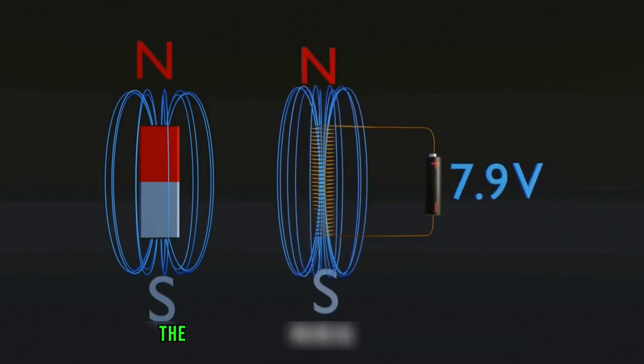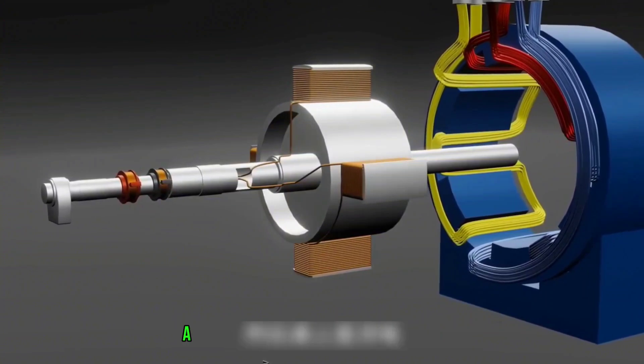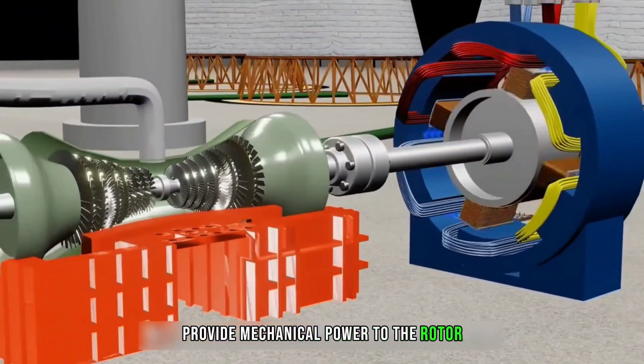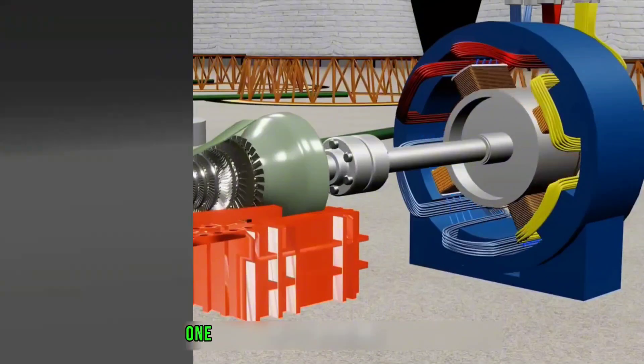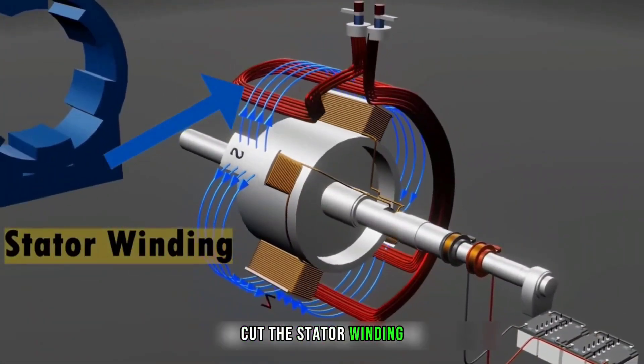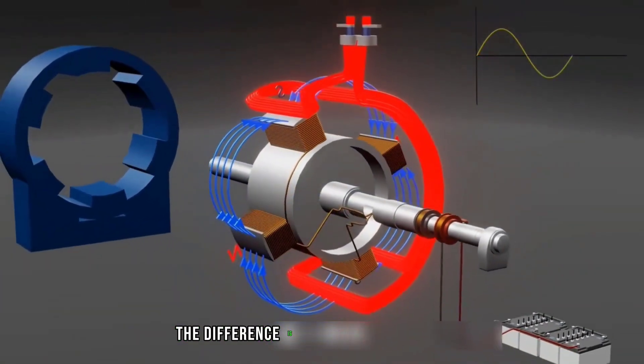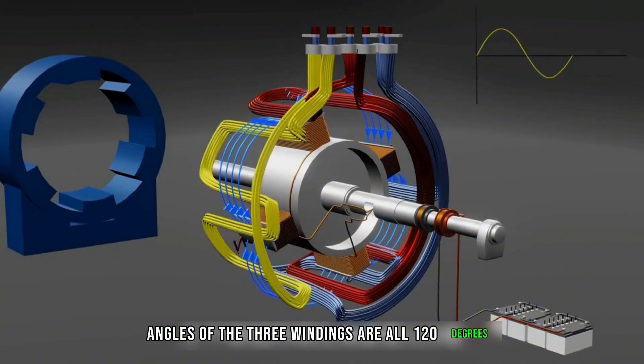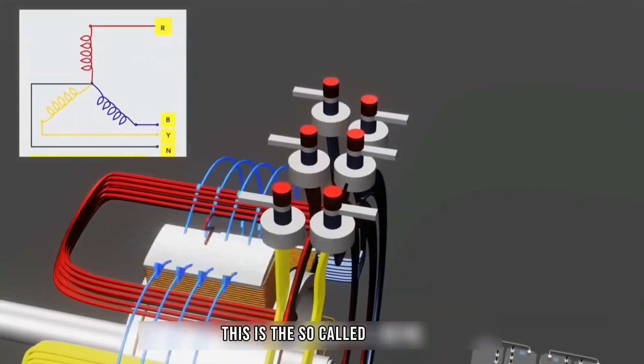We install a winding on the rotor that can generate a magnetic field, also called a field winding. When DC current is applied, a constant magnetic field is generated. We then use a turbine to provide mechanical power to the rotor. For better observation, we first show only one set of coils on the stator winding. When the rotor rotates, the magnetic field lines cut the stator winding, and the stator winding produces an electric waveform from the change in magnetic flux — the same as the simple model discussed at the beginning. The difference is that now we have three sets of windings on the stator, with phase angles of 120 degrees each. When the rotor rotates, the three windings produce electricity at the same time — this is the so-called three-phase power.